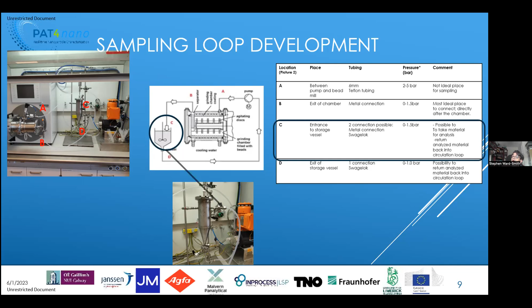Here are some preliminary results. This was a pharmaceutical active. It is active enough that we've had to persuade our health and safety people in the office that it's okay to handle it, but we've got to have the samples shipped to us as a slurry rather than produce it off-site, because we don't really have the setup for really active actives. And here you can see we can track the decrease of the particle size. We've got good reproducibility, repeating each sample multiple times. You repeated the mill run multiple times and they're getting similar answers.